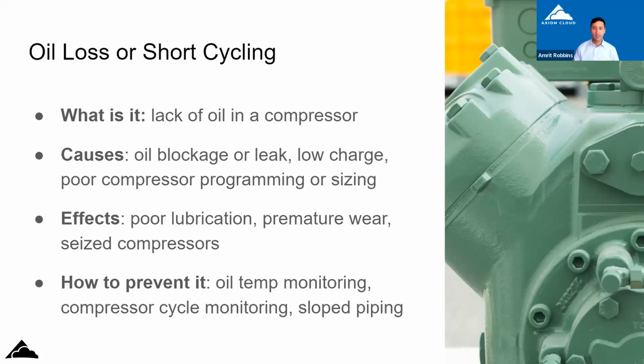Oil loss or short cycling. So obviously, when there's not enough oil in the compressor, that's bad. This can be caused by the oil line being blocked, not enough oil charge in the system, or other problems related to relative sizing of compressors versus oil reservoirs, or oil supply valves or whatnot. And so we've talked a lot about things like oil differential pressures, oil temperature monitoring, et cetera, to help identify these problems before they turn into a major issue.